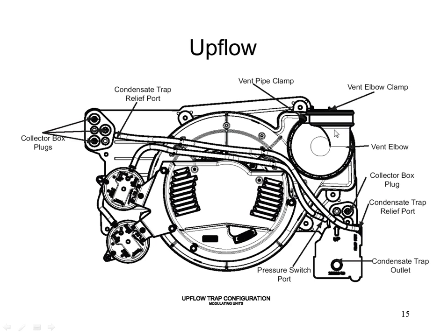The vent elbow is also very flexible to work with. There's what I'm going to call a radiator hose clamp on that guy. You loosen up that clamp, and then you can rotate this whole elbow 90, 180, or 270 degrees, depending on which way you're going to vent him. In an upflow configuration, you're obviously going to vent him up, left, or right.